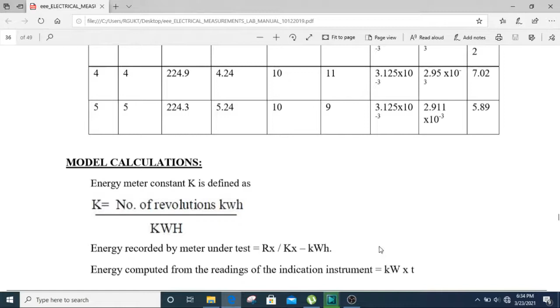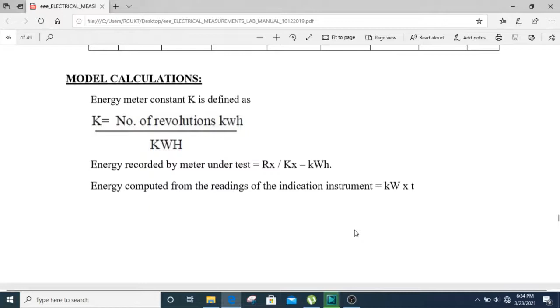Energy computed from the readings of the indication instrument, the true energy, will be equal to voltmeter reading into ammeter reading into time. Then you can find the percentage error. Percentage error is equal to the measured value, which is the number of revolutions taken by the energy meter by the meter constant. This is the measured energy.